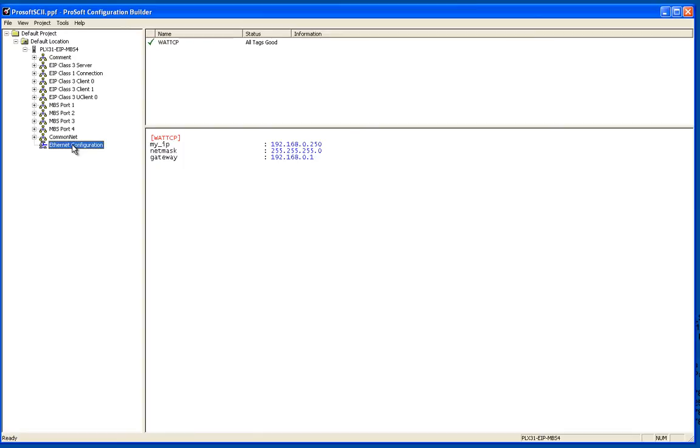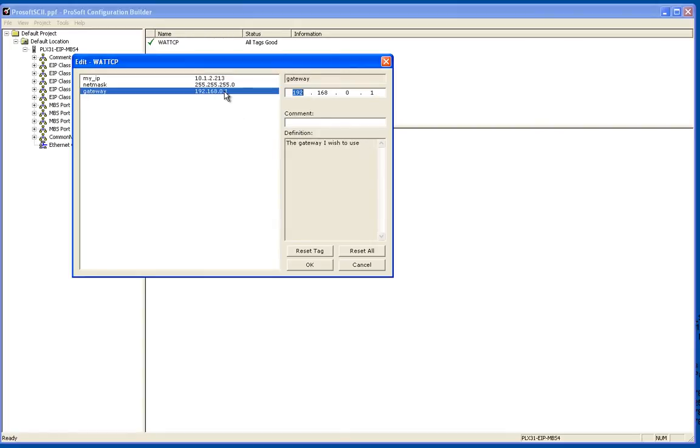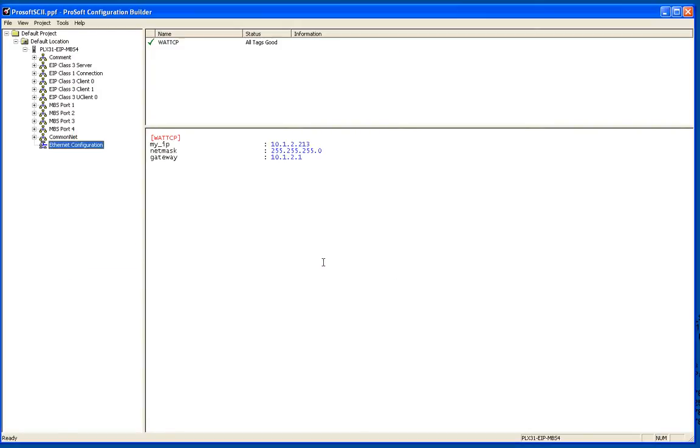First, I want to go ahead and configure my Ethernet connection. These are the settings that are going to download to your module once you choose the download option. Remember, in the Ethernet configuration this is the IP address that you want your module to have. I need mine to be 10.1.2.213 and the gateway will be 10.1.2.1. If you don't have a gateway, leave the gateway at 0.0.0.0.